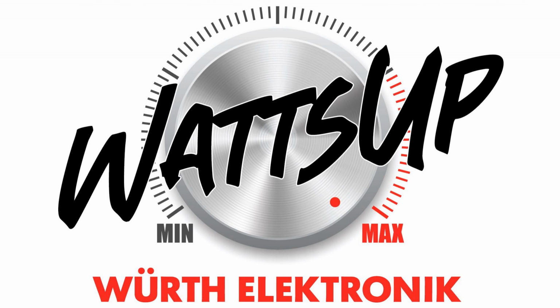The parasitic capacitance between primary and secondary sides is mainly set by the interwinding capacitance of the DC to DC power transformer device. With latest SiC MOSFETs switching at change in voltage over change in time, slew rates of 100 kilovolts per microsecond, 10 picofarads parasitic capacitance across the barrier would cause a peak displacement current of 1 amp, which is coupled by the switching transistor across the isolation barrier.